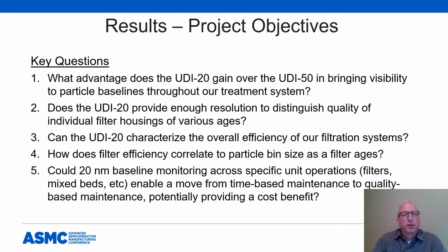For example, what advantage does the UDI-20 gain over the UDI-50 in bringing visibility to particle baselines throughout our treatment system? Second, does the UDI-20 provide enough resolution to distinguish quality of individual filter housings of various ages? Third, can the UDI-20 characterize the overall efficiency of our filtration systems?